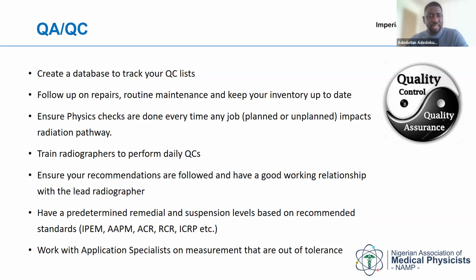Also, as a DR physicist, I said ensure physics checks are done every time any job that impacts the radiation pathway is done. So maybe they've come to change the collimator, they've come to work on the tube, they've come to work on the generator, they've come to do anything that impacts radiation, no matter how little, even if it's just about changing a filter. You want to be sure that you follow up, and then you run at least a minimum QC to be sure that everything is ideal before it is put to clinical use.